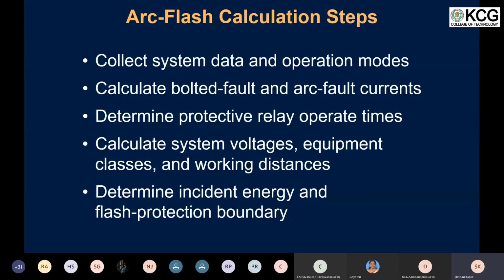Calories per centimeter square. And then there are arc flash calculation steps that are also provided by the IEEE 1584 standard. If you wish to calculate these arc flash related energies, it requires collecting the system information and the mode of operation of the relays or the switchgear, and then we need to calculate the bolted fault and the arc fault current.